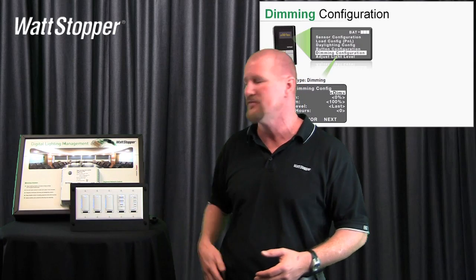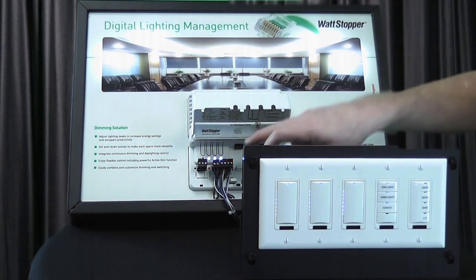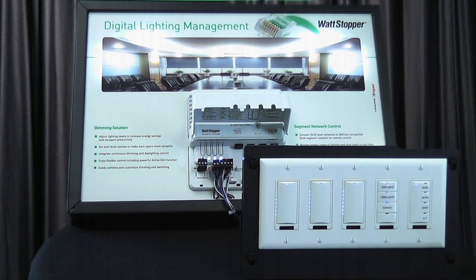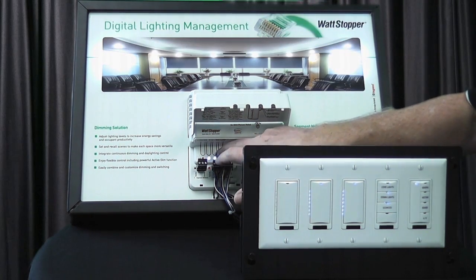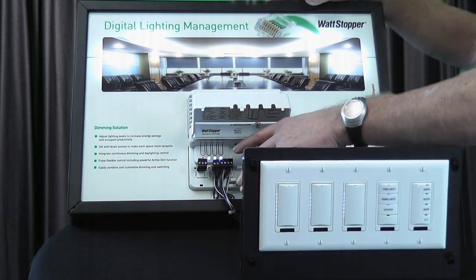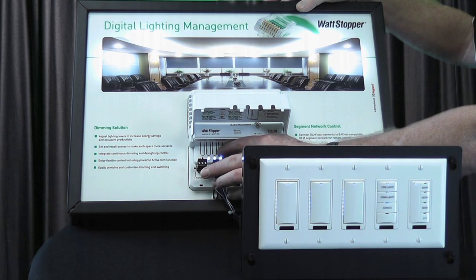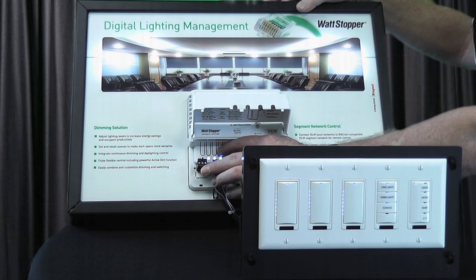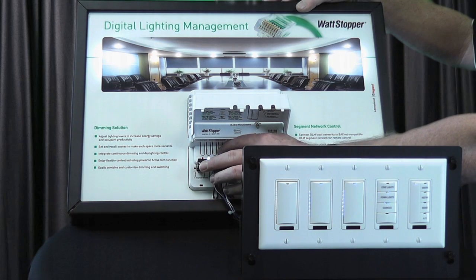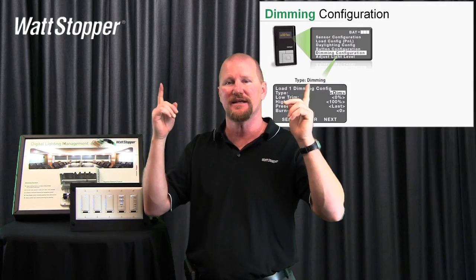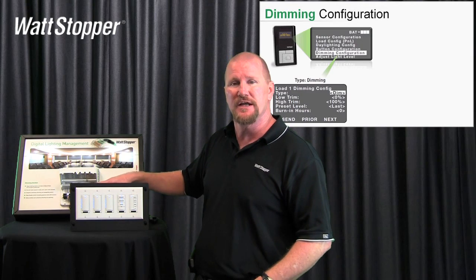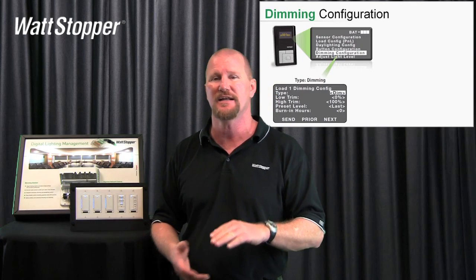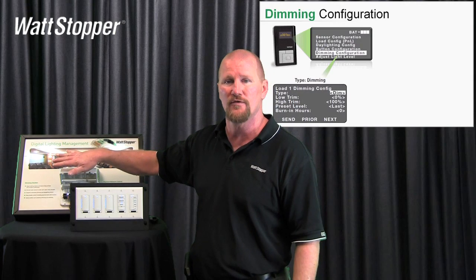The only place that you can override that trim level is at the push buttons on the room controller. We have these load control buttons on the room controller and this is an installer feature — we wanted to make sure that the installer can check his wiring. So if you look at the demo here, I will play with these cove lights. I can turn them on and off. I can also press and hold this button and dim those to make sure that my wiring is good. As I press and hold this button, you'll see that the cove light dims, and after a couple of seconds it's going to start brightening back up. Now, if I turn it off in a dimmed position, when I turn it back on it's going to come on to full bright. The reason for that is I'm an electrician — my head's in the ceiling and the lights are down below, so when I press that button I need to see that those lights came on. So we put that feature in so that the electrician can test his wiring, and I didn't want somebody who set a high trim at 50% to have the electrician not see that the lights came on. This is the only place that will override high and low trim.